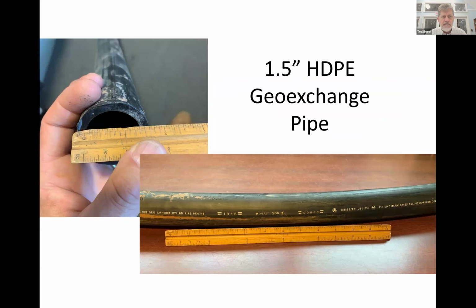This gives you an example of the size of pipe. We drill a 6-inch hole in the ground, go 850 feet down, and take this pipe, fabricated in the shape of a U, like a soda straw. It goes down, bends 90 degrees, and comes back up. We stuff it 850 feet into the ground, then fill the outside of the pipe and the inside of the drilled hole with grout. So it's basically a super tough pipe encased in concrete and rock. I fully expect it will still be there a century from now, functional and working fine. It's designed specifically for this application.